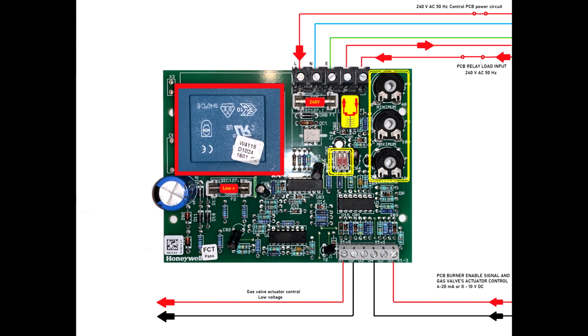And you really have to pay attention, because on some occasion I found one air handling unit which runs on a Reznor burner, and these printed circuit boards were enabling the burner even if the programmable logic control or building management control was not sending voltage to it. I mean, the voltage was 0.5, probably a tiny leak enabled this burner without the supply fan, and that could lead to a disaster.